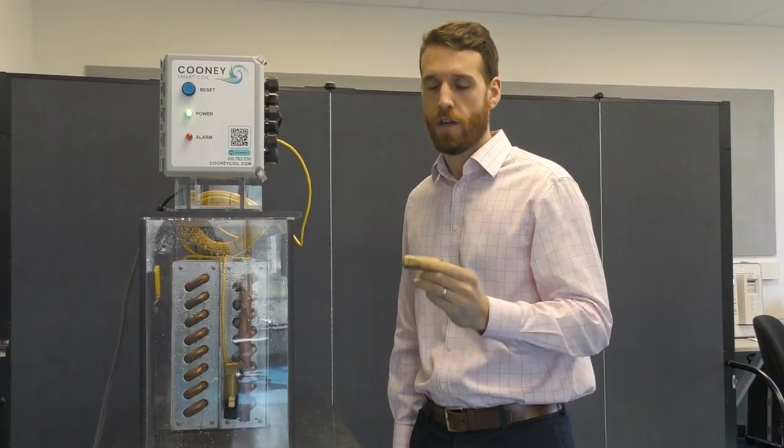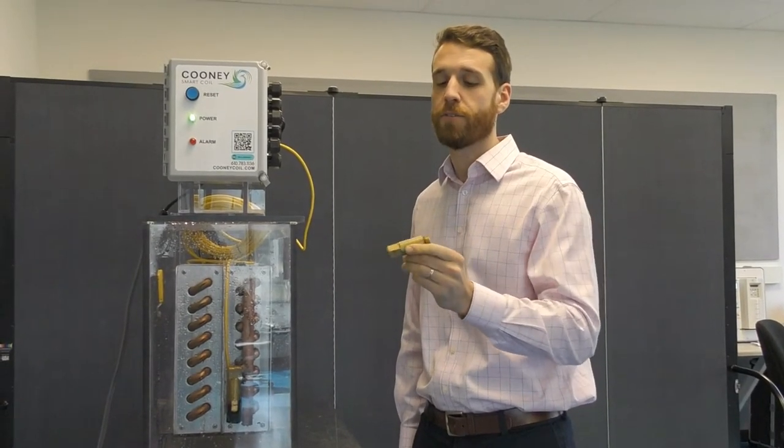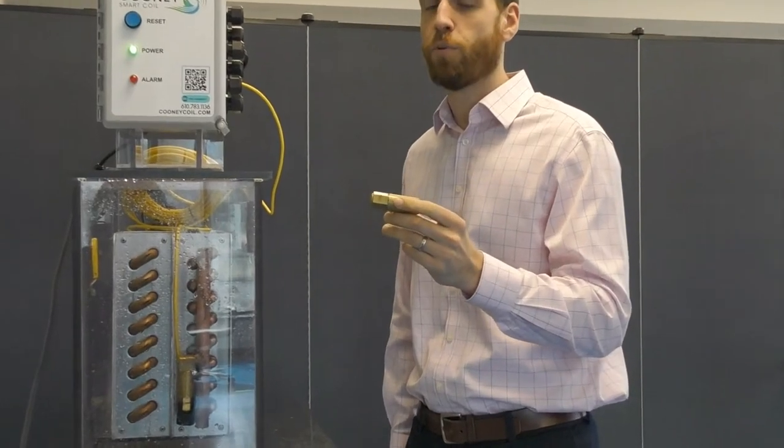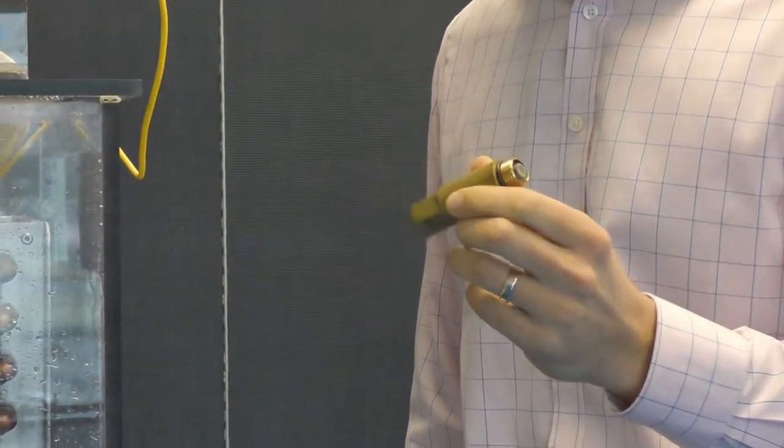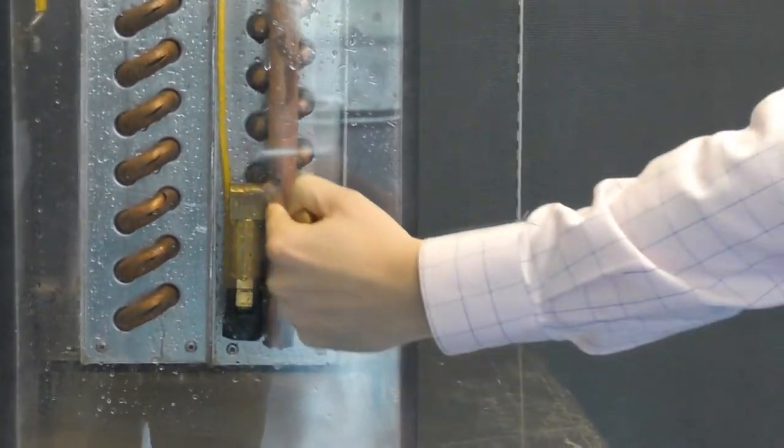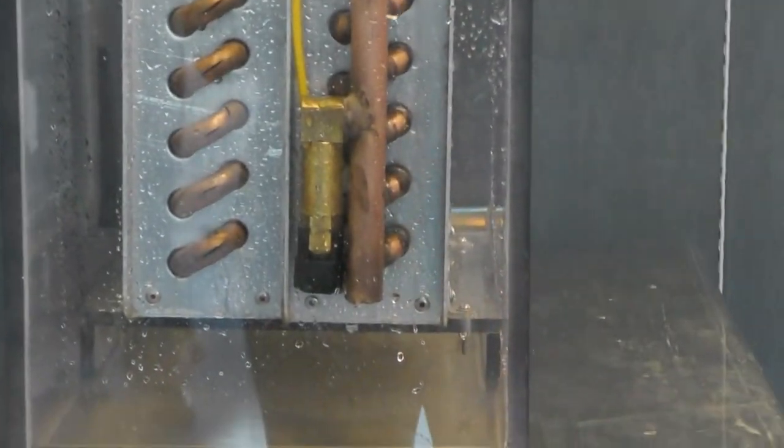We have a better solution. The magic behind the Cooney coil system is this valve, and this valve will discharge controlled amounts of liquid from the coil based on pressure or temperature. You'll see this valve mounted on the return bend of the coil here.